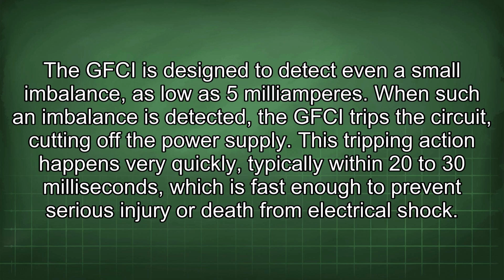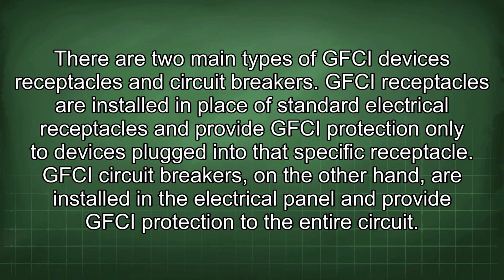When such an imbalance is detected, the GFCI trips the circuit, cutting off the power supply. This tripping action happens very quickly, typically within 20 to 30 milliseconds, which is fast enough to prevent serious injury or death from electrical shock. There are two main types of GFCI devices: receptacles and circuit breakers. GFCI receptacles are installed in place of standard electrical receptacles and provide GFCI protection only to devices plugged into that specific receptacle.